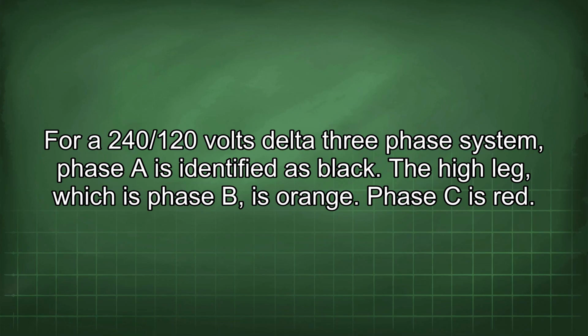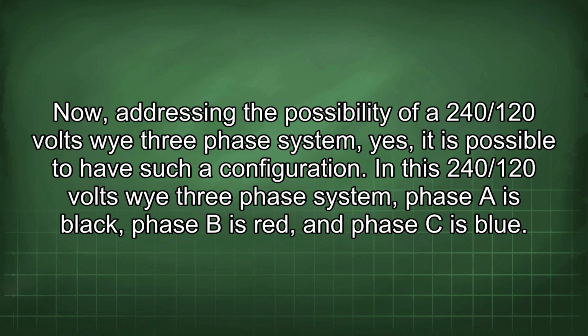For a 240/120 volts delta 3-phase system, phase A is identified as black. The high leg, which is phase B, is orange. Phase C is red. Now addressing the possibility of a 240/120 volts Y 3-phase system, yes, it is possible to have such a configuration.